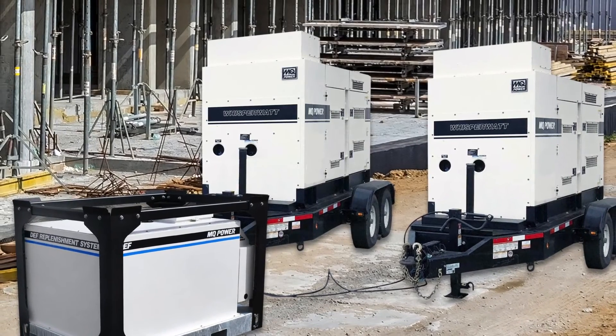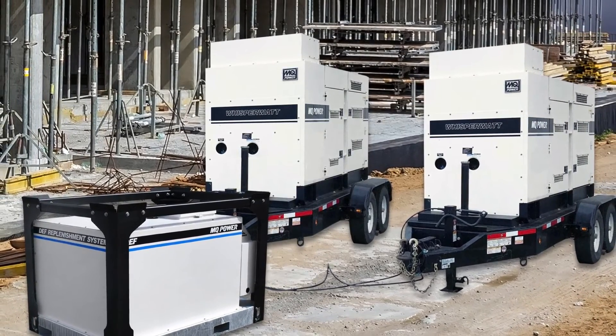The applications in many cases require additional fuel tanks or auxiliary fuel tanks. And without an external DEF replenishment system, you will run out of DEF from the internal reservoir on the generator well before you run out of your external fuel tank. That would pair up really well for a single generator on a remote site.